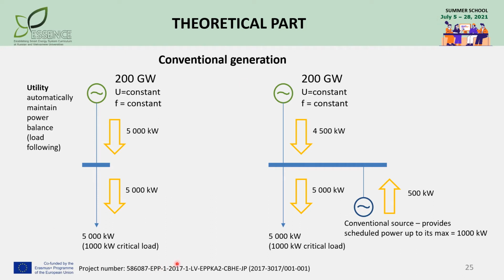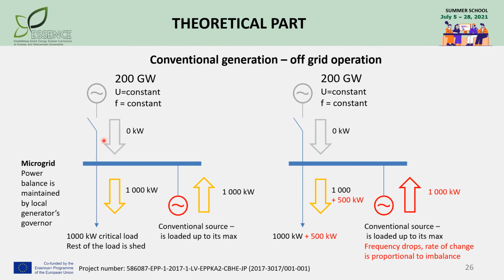If we add a conventional distributed source with the size adequate to supply critical loads in case of islanding, it may also be operated during normal conditions to cover base load and hold speed reserve. When the microgrid turns to islanded mode, the generator is loaded up to its max limit to supply the critical loads, and the rest of consumption shall be disconnected to ensure real power balance.